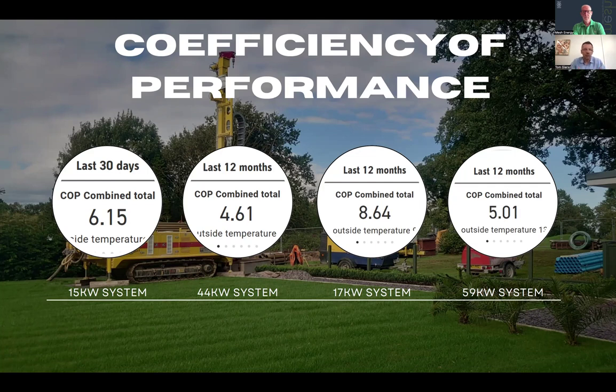If some rooms in the house are calling for heat, they will draw this 28 degrees from the buffer tank and deliver this to the house. The buffer tank will drop temperature, and then the heat pump, after some time when the temperature drops by some numbers, will kick in again to try to maintain or top up the buffer tank to 28 degrees. Heat pumps are not running like boilers all the time, on off, on off. Otherwise, you will kill the compressor too quick.